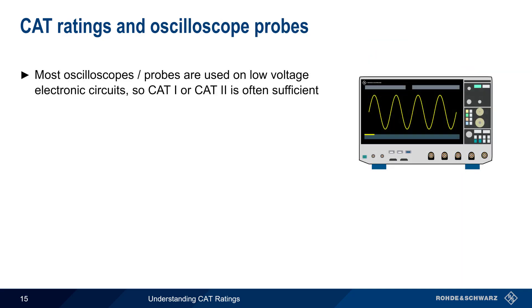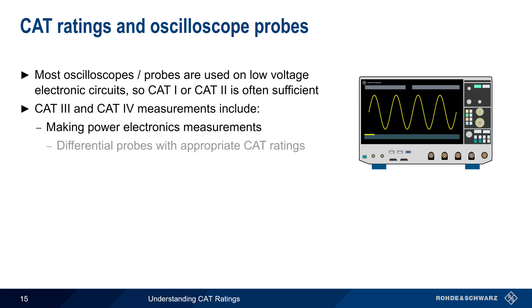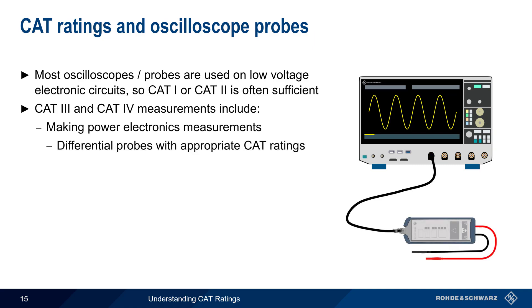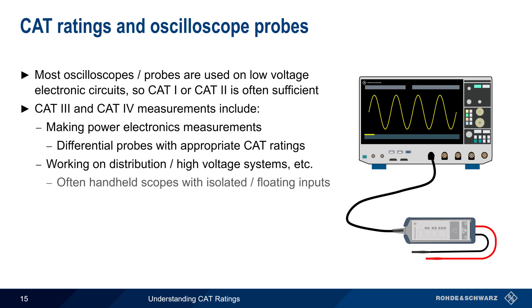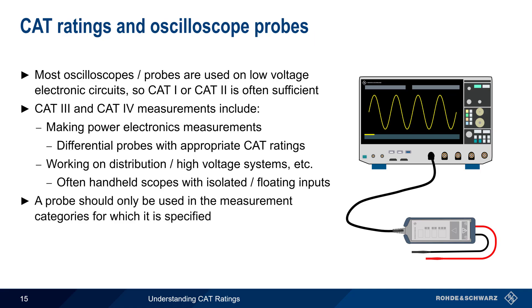Most oscilloscopes are used in lab or R&D environments on relatively low voltage electronic circuits, so a CAT 1 or CAT 2 rating is usually sufficient for most oscilloscopes and probes. Examples of CAT 3 and CAT 4 measurements include power electronic measurements, which normally use differential probes with appropriately higher CAT ratings. Another example is measurements made on distribution or higher voltage systems, typically done using handheld oscilloscopes with isolated or floating inputs for additional safety. Regardless of the application, a probe should only be used in the measurement category for which it's specified.